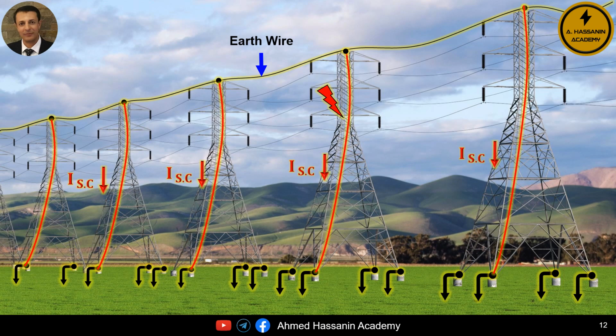The metallic tower structure has resistance or impedance, and we all know that when resistances or impedances are connected in parallel, the total equivalent resistance or impedance decreases. Hence, we understand that the resistance or impedance of the tower structure will decrease as long as all the towers are connected in parallel. This, of course, will provide an easy path for earth fault currents. As we can see in front of us, the earth fault currents are distributed among the adjacent towers.